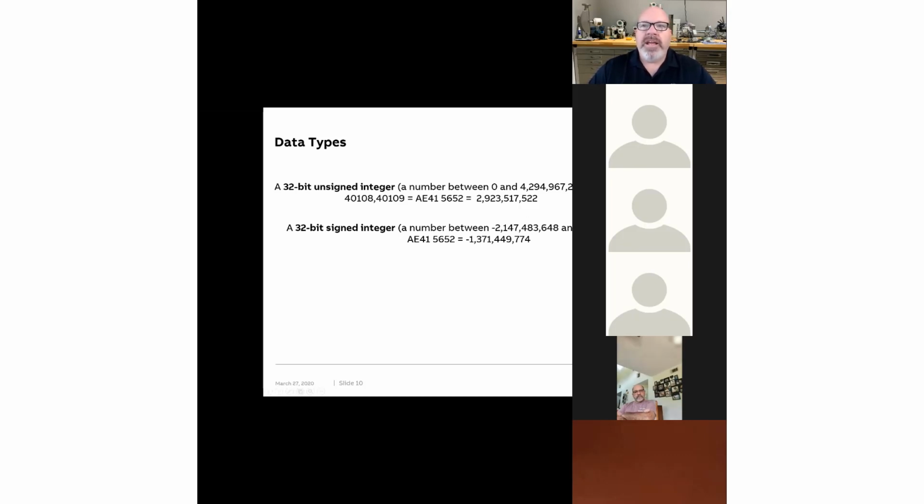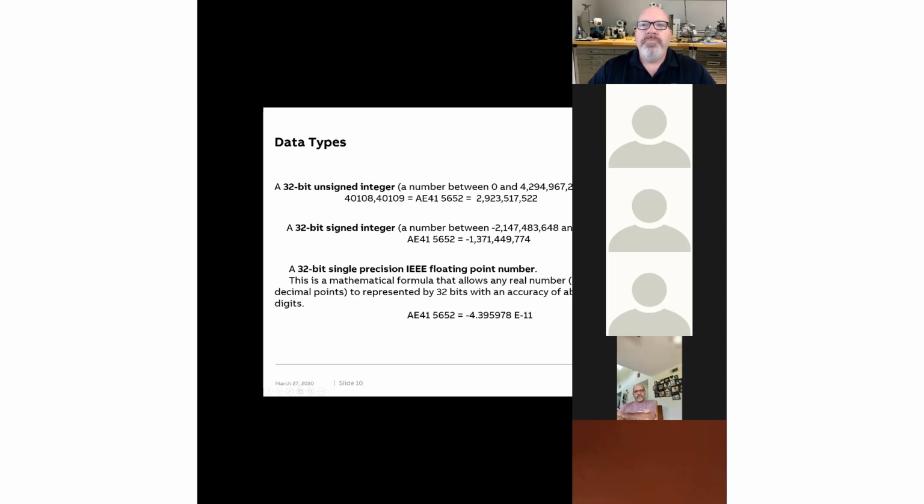But I'm bringing those back as a 32-bit integer, which means that over time, the biggest number that I'm going to be able to get is basically 2,147,000. So once my pulse accumulator goes above that, once my volume totals, once my mass totals go above that, I can't transmit a number any higher because I'm using a 32-bit integer.